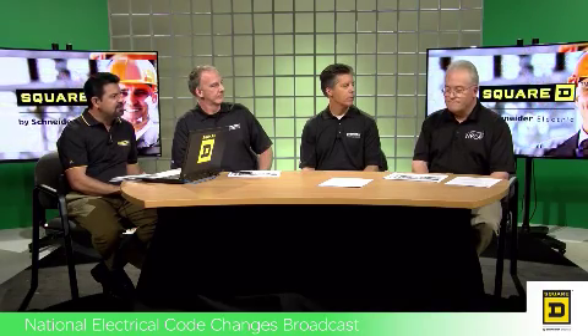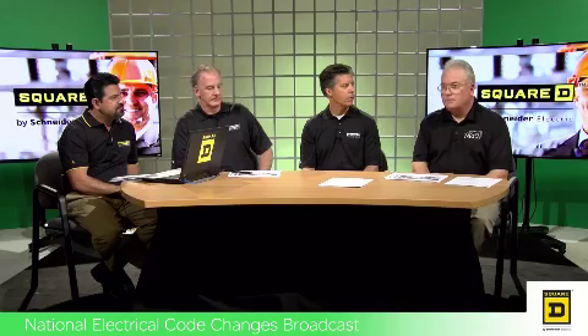Great, thank you, Alan. So Mike, the next question I have for you is, what are the changes, or how are they impacting the changes in single-phase dwelling feeders in Article or Section 310? Yeah, thank you, Phil. That's a good change for industry. It actually takes Section 310.15(B)(7) and expands it to 208Y/120 systems from the 120/240 volt system. So that's the big thing that you'll notice in 310.15(B)(7).